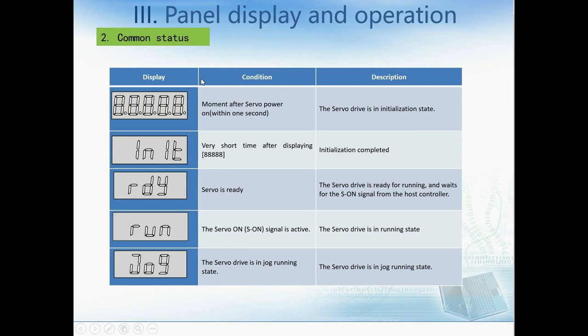Here are some common messages we can see on the LED. The first is '88888', which means the servo drive is in initialization state. The second is 'Init', meaning initialization is completed. The third is 'RDY', meaning the servo drive is ready and waiting for a servo-on signal from the host controller. The fourth is 'RUN', meaning the servo drive is in running state. The last is 'JOG', meaning the servo drive is in JOG running state.